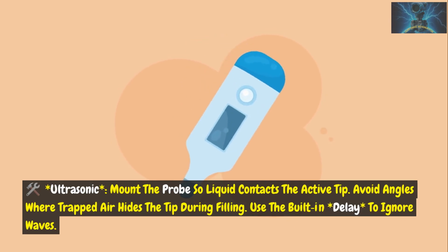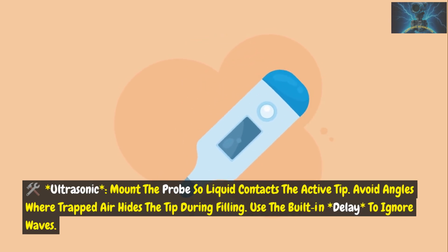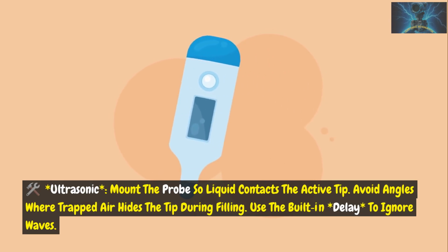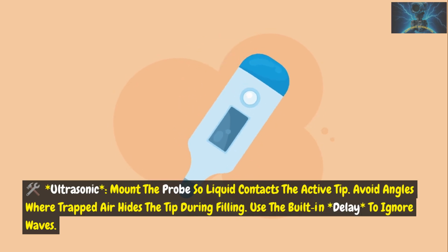Ultrasonic: mount the probe so liquid contacts the active tip. Avoid angles where trapped air hides the tip during filling. Use the built-in delay to ignore waves.